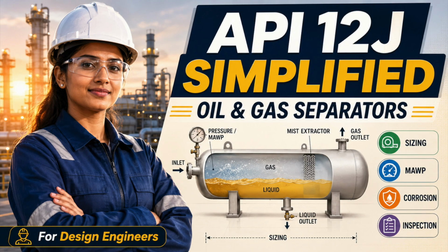The normal control level, alarm levels, and shutdown levels must therefore be selected from process consequences, not arbitrary percentages of transmitter span. You need to ask how much time exists between high level and high-high level. How quickly can the upstream source be isolated? How fast can the outlet system respond? Is the control valve oversized? Is the measurement stable in foam or emulsion? Can the operator verify the reading?